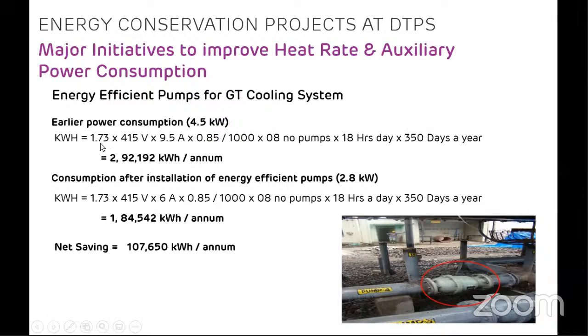So considering this, if we calculate the kilowatt hour consumption, now if you may be aware or not, the formula for calculation of kilowatt hours from kilowatt is: we take root 3, which is 1.73, 415 volts, 9.5 ampere is the current, and 0.85 is the power factor, and 1000 is for converting watt to kilowatt. And there are 8 such pumps running 18 hours a day for 350 days a year. So we get 2,92,000 kWh per annum.